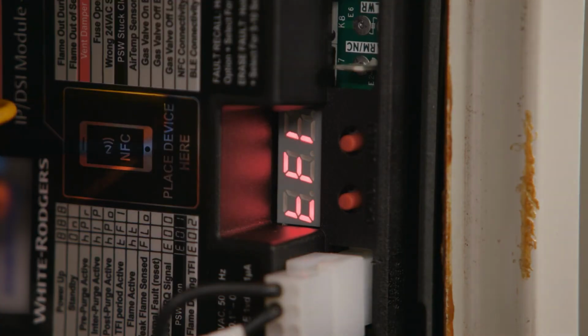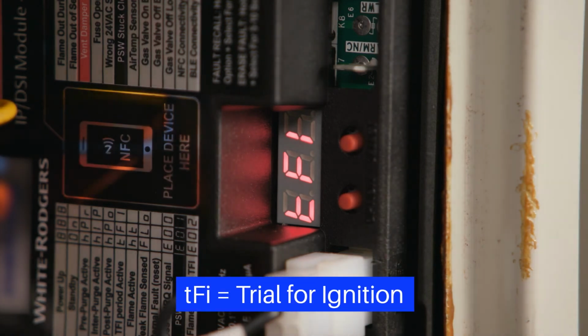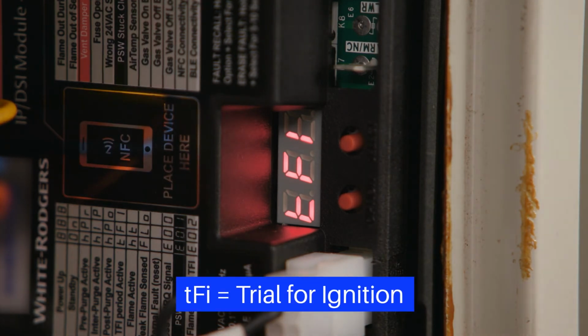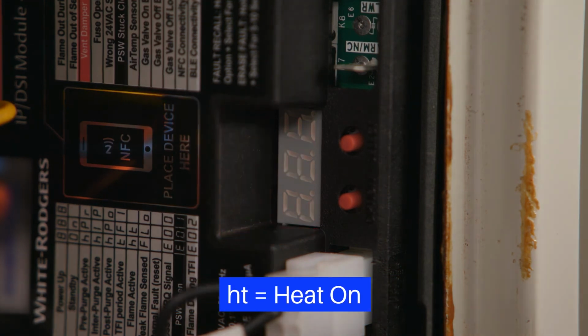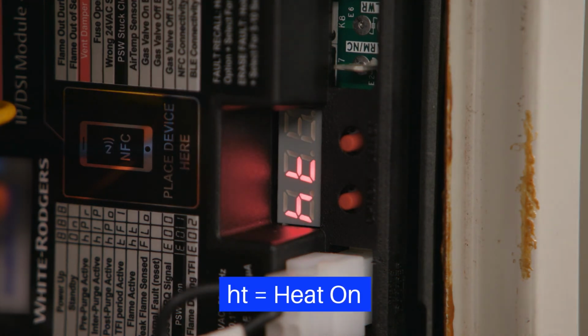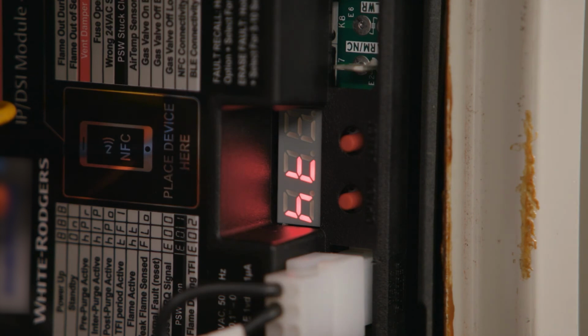For this intermittent pilot application, it will first display the letters T, F, and I, indicating it is in a trial for ignition period. After the flame is active, the LEDs will display the letters H and T. When a weak flame is sensed during operation, the LEDs will toggle between the letters H, T, and FLO, indicating the flame probe needs checked.